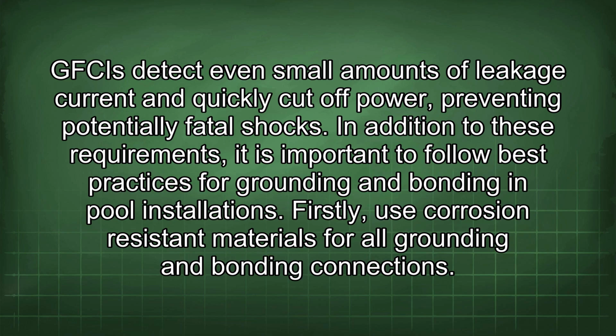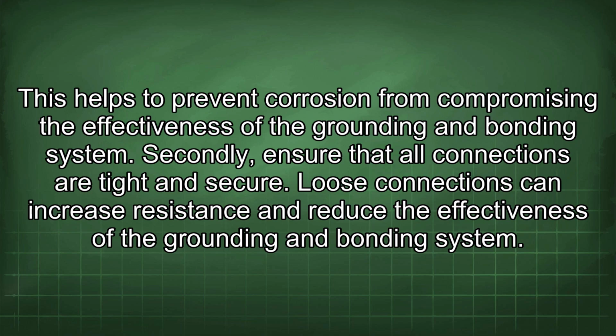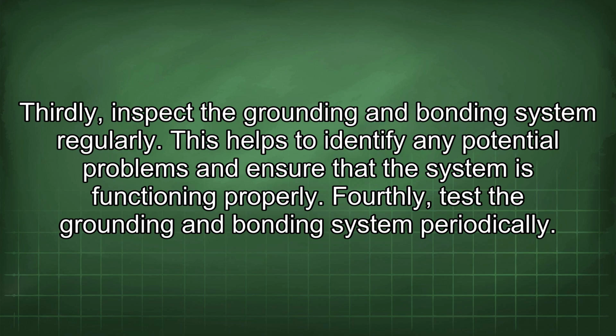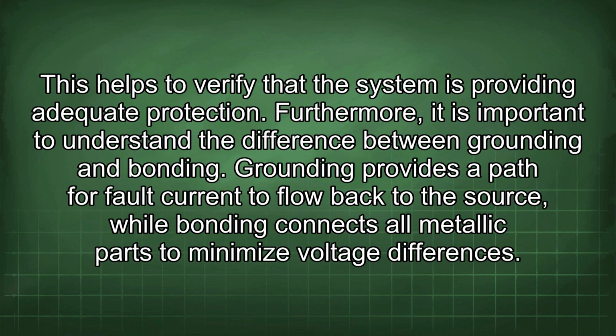In addition to these requirements, it is important to follow best practices for grounding and bonding in pool installations. Firstly, use corrosion-resistant materials for all grounding and bonding connections. This helps to prevent corrosion from compromising the effectiveness of the grounding and bonding system. Secondly, ensure that all connections are tight and secure. Loose connections can increase resistance and reduce the effectiveness of the grounding and bonding system. Thirdly, inspect the grounding and bonding system regularly. This helps to identify any potential problems and ensure that the system is functioning properly. Fourthly, test the grounding and bonding system periodically. This helps to verify that the system is providing adequate protection.